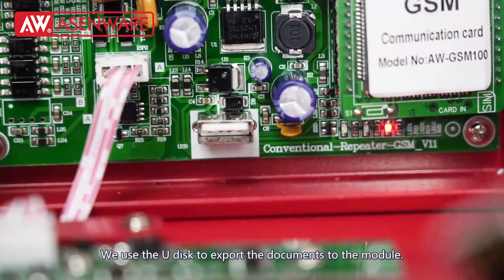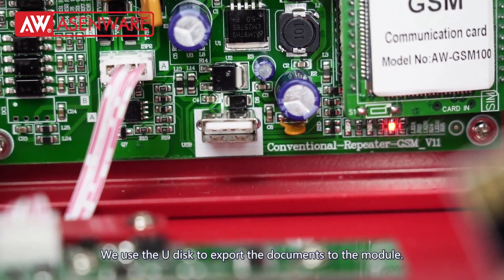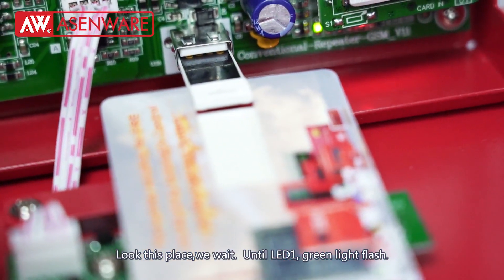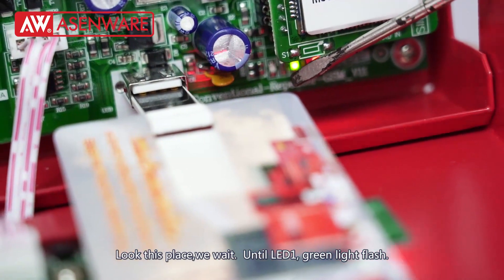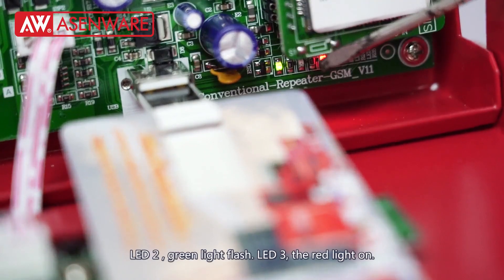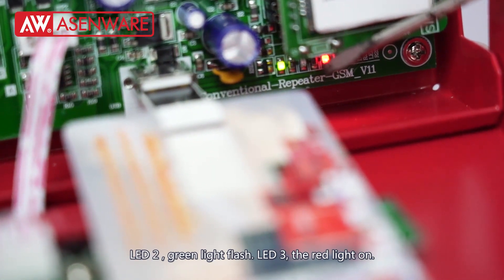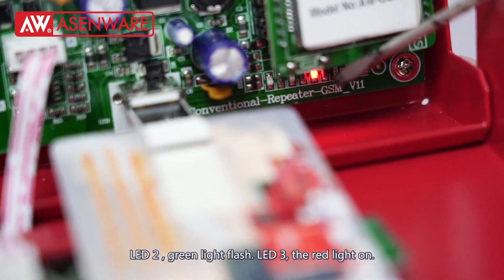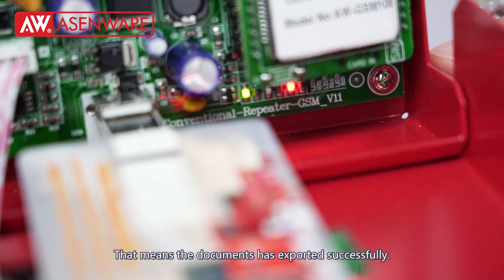Then we use the U-Disc to export this document to the module. Look at this place. We wait until LED 1 flashes green, LED 2 flashes green, and LED 3 shows a red light on. That means the document has been exported successfully.